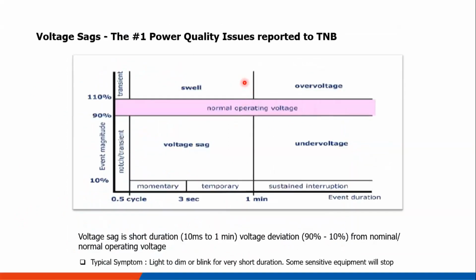So, based on the standards, we consider swell and sag. Today, my slide will focus on sag. So, voltage sag is actually defined as a short duration from 10 milliseconds to 1 minute for voltage deviation 90 to 10%. So, any voltage that falls below 90% of the nominal voltage to 10% of the nominal voltage is considered sag. So, what are the symptoms of voltage sag? Lights dim or blink for a short duration, and some sensitive equipment which does not have enough immunity will stop.